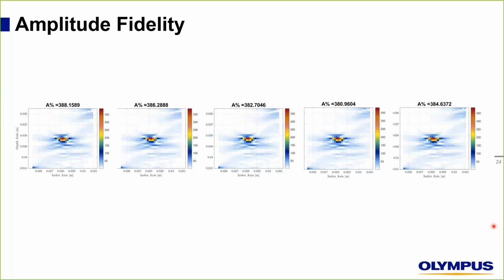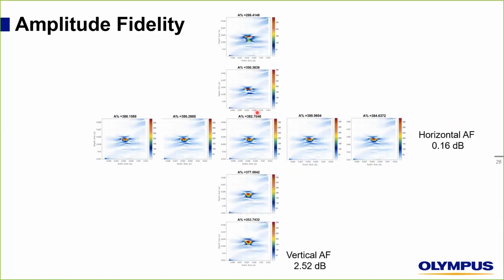So as you can see here, we moved the grid a little bit. We are reading the amplitude here. It's like the full screen height reading that is provided on phased array machines. And we can see there is a slight variation that indicates a little difference in dB when we move the grid to the left or to the right. Same thing for the vertical axis as well. And actually here we see that we have a 0.16 dB difference on the horizontal axis and 2.52 dB on the vertical axis.